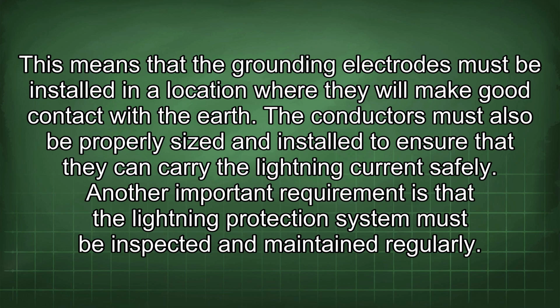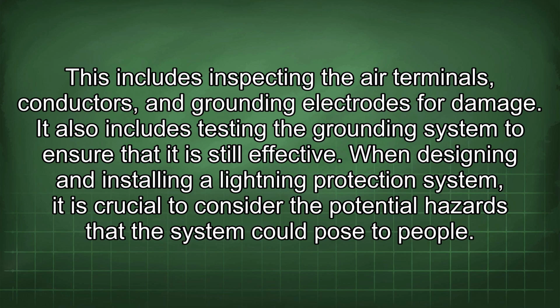Another important requirement is that the lightning protection system must be inspected and maintained regularly. This includes inspecting the air terminals, conductors, and grounding electrodes for damage. It also includes testing the grounding system to ensure that it is still effective.